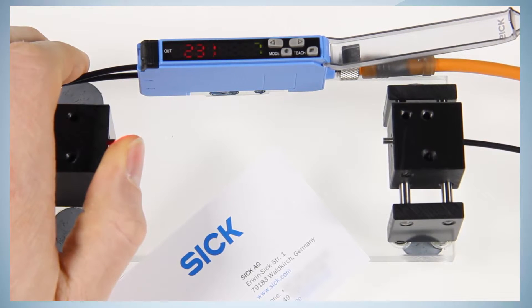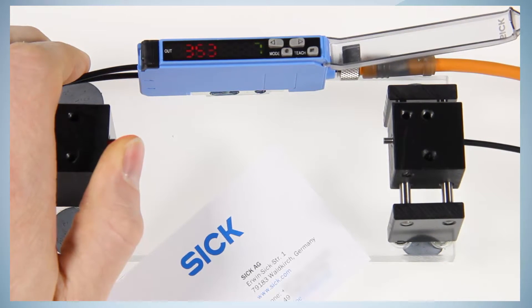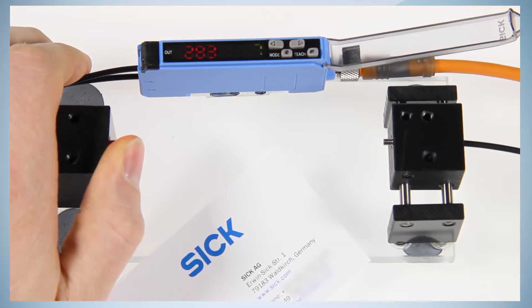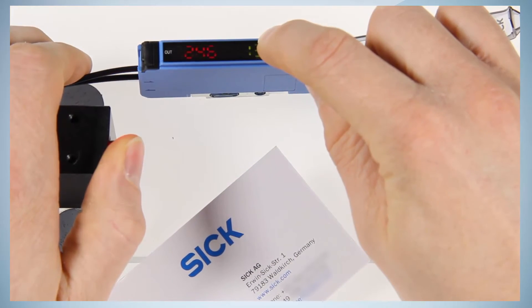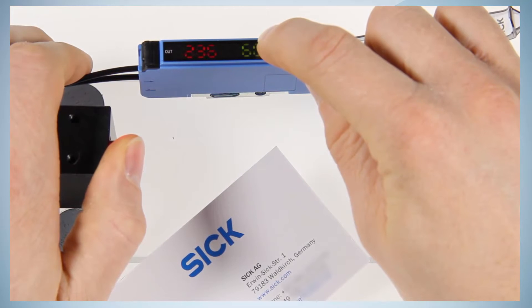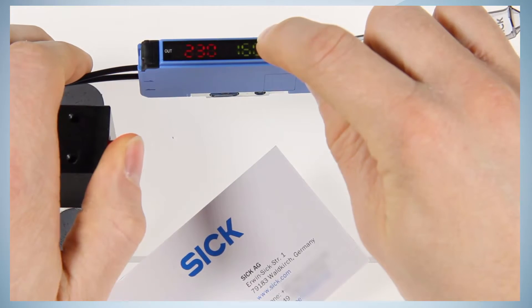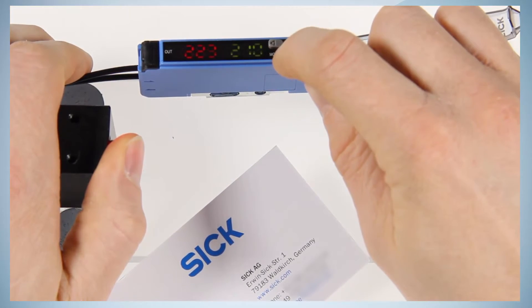The received light should still result in approximately 300 digits. Now set the switching threshold below the value which is received with the contamination of your finger. In this case, below 300 digits to for example 200 digits by using the plus or minus button.